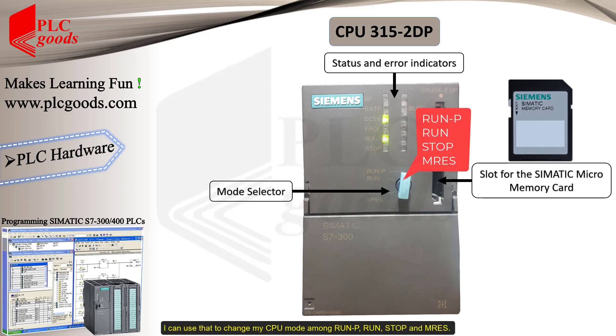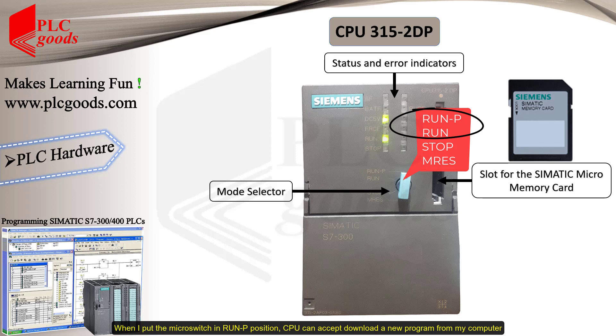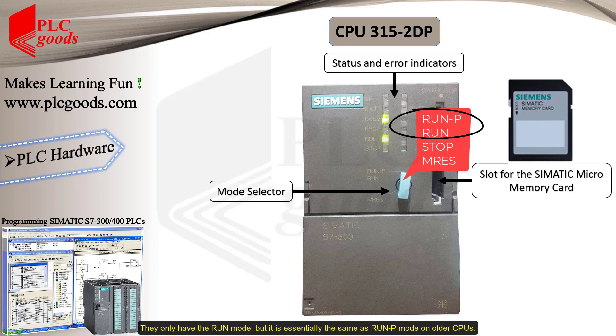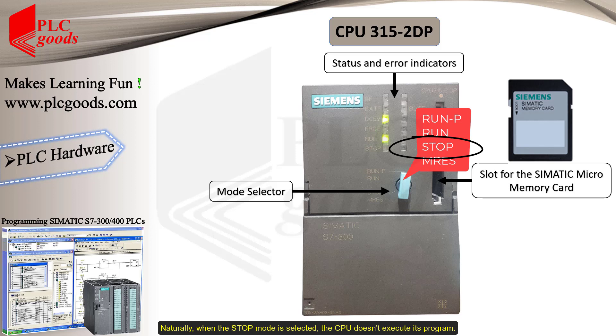After the indicators, this empty slot can be used to insert a SIMATIC Micro Memory Card. The next important part is this mode switch. I can use it to change my CPU mode among RUN-P, RUN, STOP, and Memory Reset. When RUN-P or RUN mode are selected, the PLC executes its program, but with a small difference: in RUN-P position, the CPU can accept and download a new program from my computer, whereas in RUN mode the PLC will reject any changes or downloads. Note that newer CPUs don't have a RUN-P position — they only have RUN mode, but it functions essentially the same as RUN-P on older CPUs. When STOP mode is selected, the CPU does not execute its program.